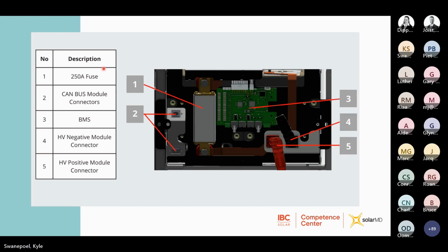All right. Just again, here's your fuse. Number 2 over here, you've got the CAN bus communication connection point for the module. So this is just to make the connection easier for you. Because the solution is modular, the adding and removing of battery modules does mean that you'll need to be hands-on regarding the connection and the commissioning of the battery. So the internal communication over here is connected to the frame connectors here. Your top connector will go to your first BMS port, CAN bus 1 over here. And then the bottom frame connector here will go to the CAN bus 2 port 2.